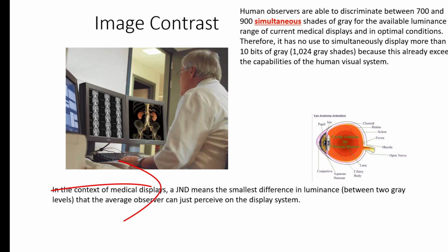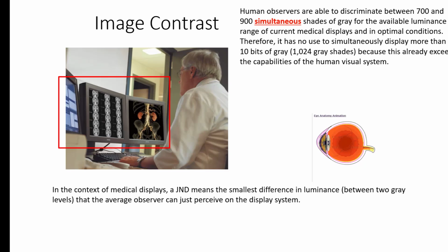So how do we figure out this contrast thing for the monitors? Well, it's not like the monitor you would buy. Yes, I can go to Best Buy and buy a 3 megapixel monitor or a 5 megapixel monitor, which would be very cheap compared to a medical monitor. Medical monitors are designed and calibrated totally differently than commercial monitors that are used just for TV or computers.